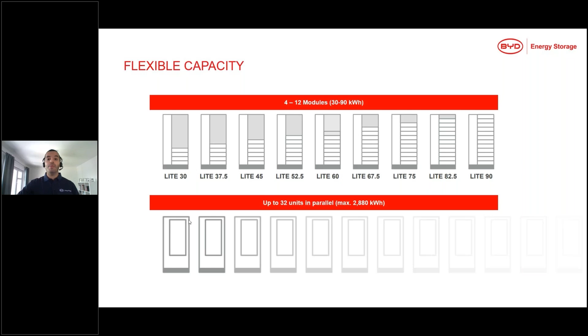Here you see a screenshot of the datasheet, and you see again that it's a real high voltage system. Those modules are connected in series, not in parallel, within a rack. And because of that, you have a high voltage. So even the smallest configuration with 4 modules and just 30 kilowatt hours has a voltage of 300 volt. And if you have the full-blown stack with 12 modules inside, then you already have a voltage of over 900 volt. Again, those systems are flexible because the Max Lite can also be extended at any given time. The main difference is that you don't put the modules on top of each other, stackable, but instead you have to open the door and put the modules inside like a drawer system. So here again, very flexible.